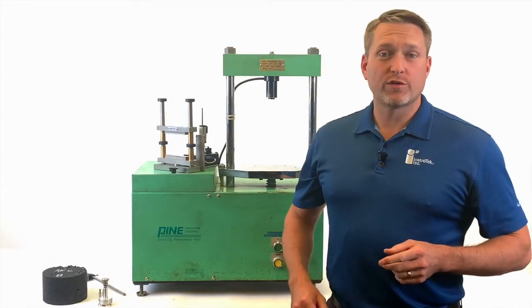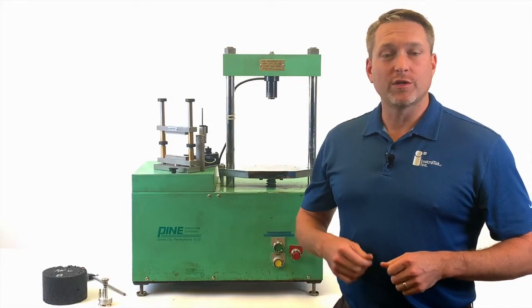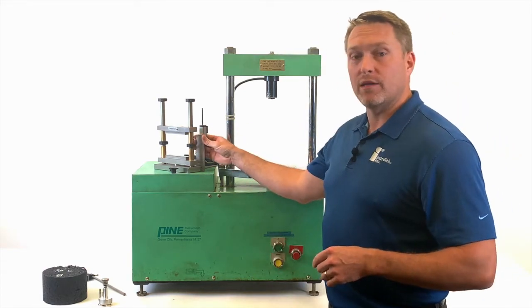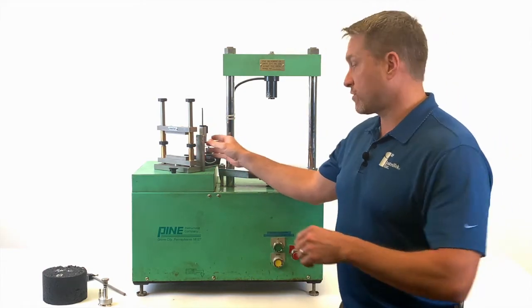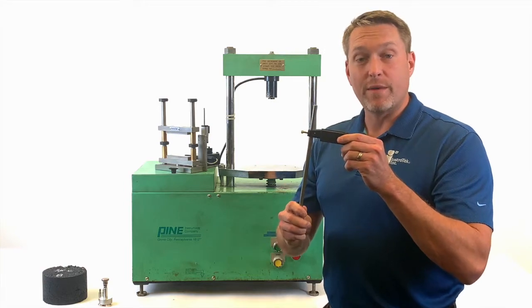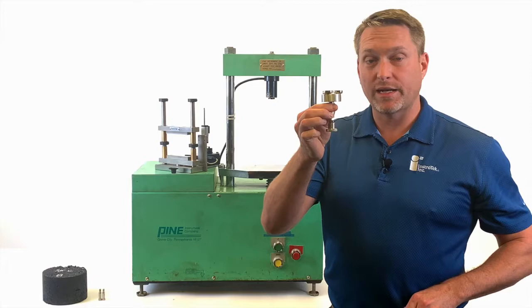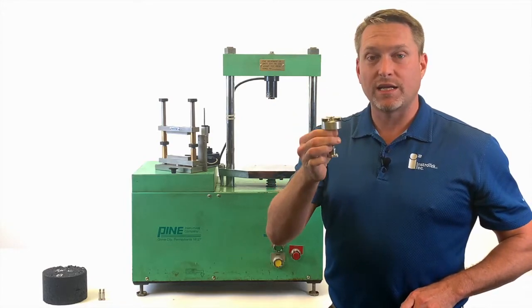There are two different versions of the Smart Jig, and we're going to show you how to align each one individually. The first version has the LVDT bracket located in the back of the Smart Jig, or facing towards the back. The reason that we did this is this was the version 1 of the magnet. We have since changed to this style for the contact magnet. If you don't have one of these, please contact InstroTek.